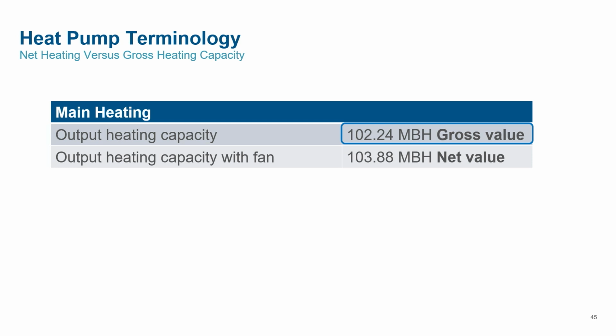A heat pump, on the other hand, welcomes the additional heat source. The result of the additional heat impacts the leaving air temperature and may result in an inverted gross versus net capacity value. The air-to-air heat pump coefficient of performance, or COP, can be summarized in one word: efficiency. For example, a resistive heater provides 1 watt of electric heat for every watt purchased. This is called 100% efficient, or a COP of 1. The output is the same as the input.